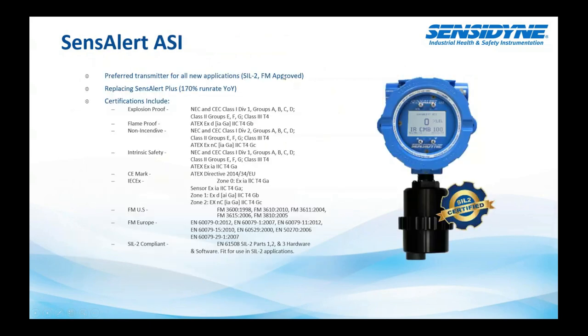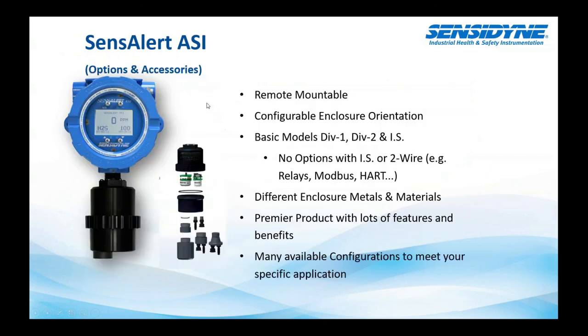So as I said, the SensAlert ASI is our preferred transmitter for all new applications. It is still CSA certified, FM approved, and replacing the SensAlert Plus. So if you have some SensAlert Plus in here, this is your next generation of the instrument. It is remote mountable, like we discussed, with the sensor up to 100 feet away from the transmitter. There is configurable enclosure orientation, so if you have an orientation where your connections are either on a horizontal or vertical plane, we can orient that. So for existing installations, we can accommodate that as well.